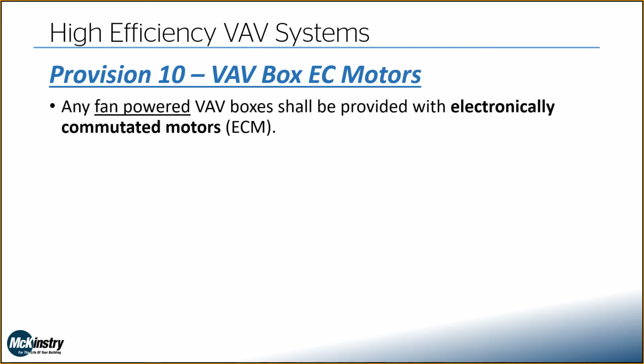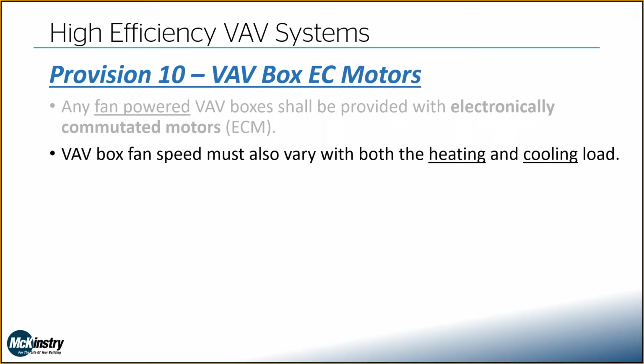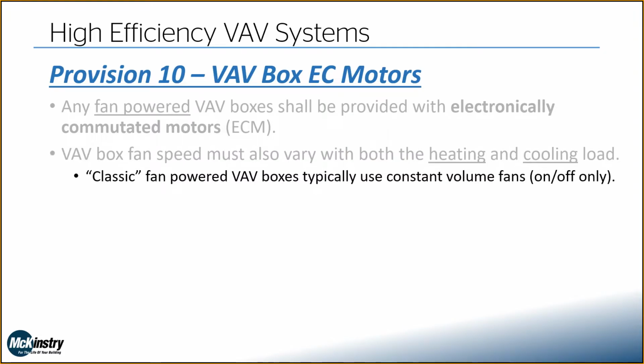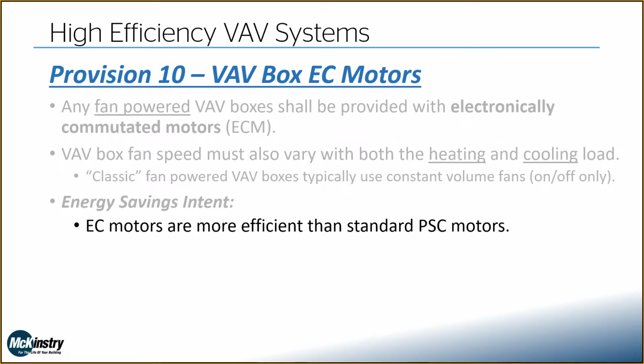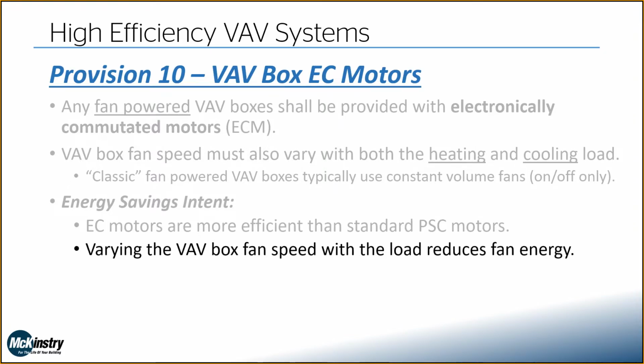VAV box EC motors. If we have any fan-powered VAV boxes, these have to have electronically commutated motors, or ECM. Additionally, your box fan speed must also vary with both the heating and the cooling load, which is a little different than what we're used to. In what I'm calling classic fan-powered VAV design, usually these fans are constant volume fans. They're either on or off, so you're getting full airflow or nothing. The intent here: EC motors, right out the gate, are more efficient than standard PSC motors, but we can also save some fan energy by varying the box fan speed with both the heating and the cooling load.